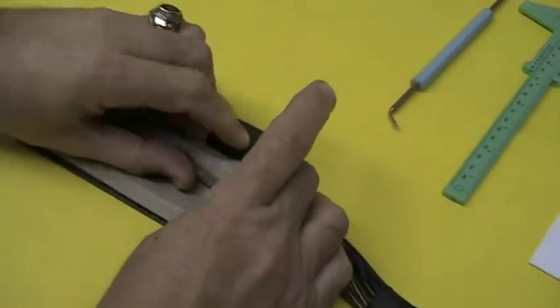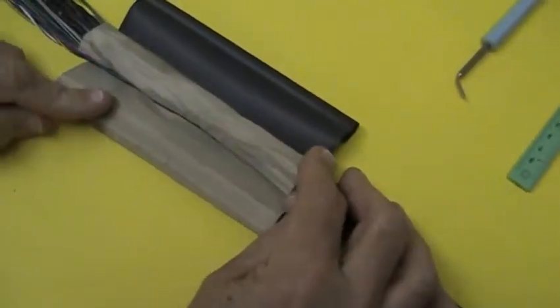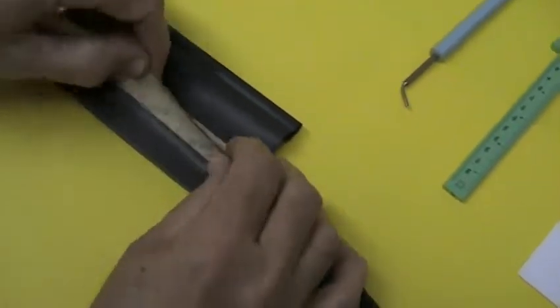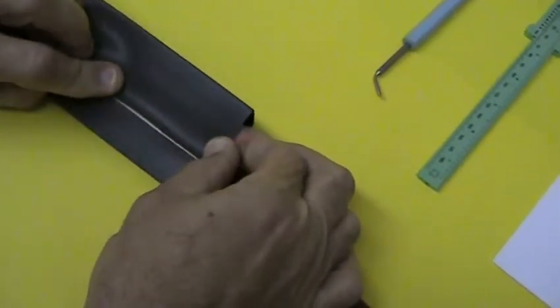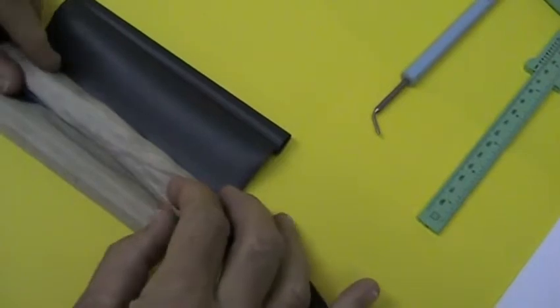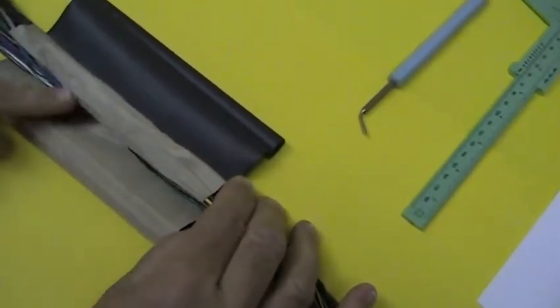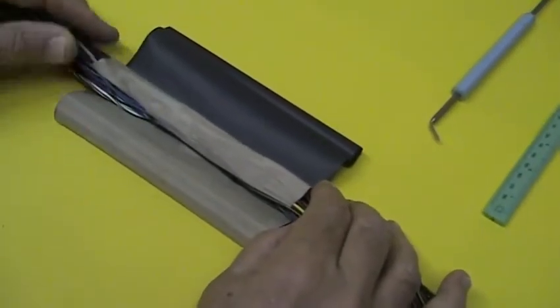Now once that edge is stuck to the cable, we have almost 360 degree shield coverage at the moment. When I wrap the rest of it around and stick the PRT tubing together and start to shrink it, this will snail up and the overlap will increase. The reason for the adhesive is so this edge can't move and you always ensure that you have full shield coverage.